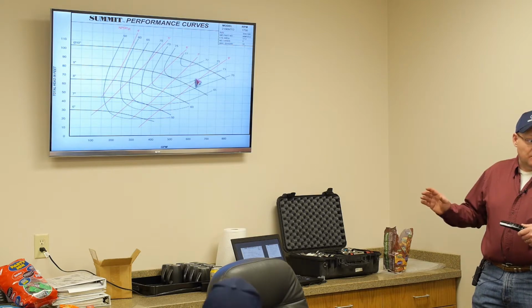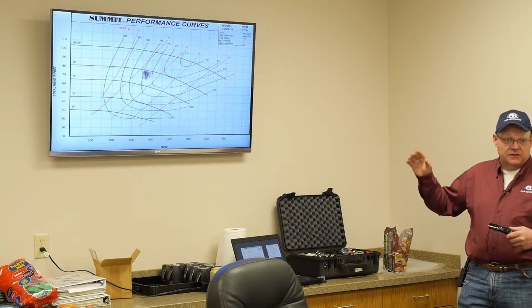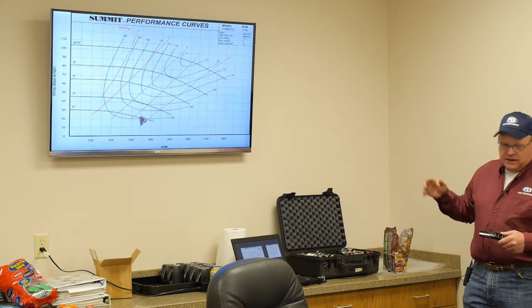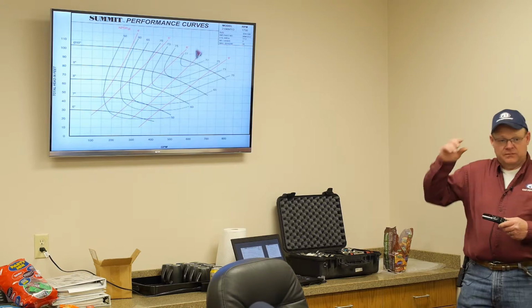It's a lot more important when you're running to the right-hand side of the curve to have plenty of NPSH. That's why I said, remember that nominal pipe size, one size bigger? You don't have that friction loss going into the suction side of the pump.